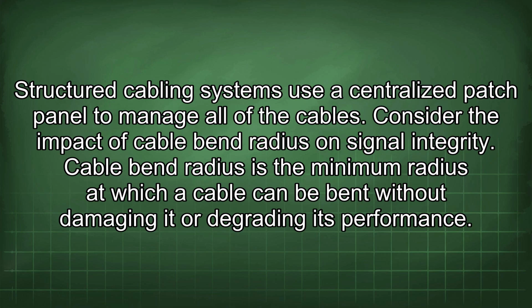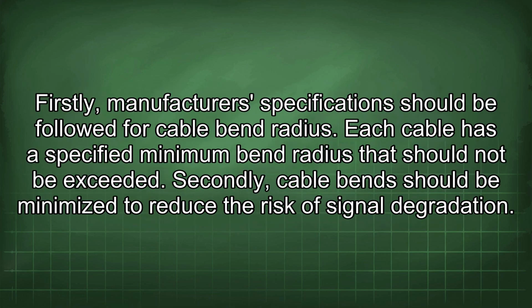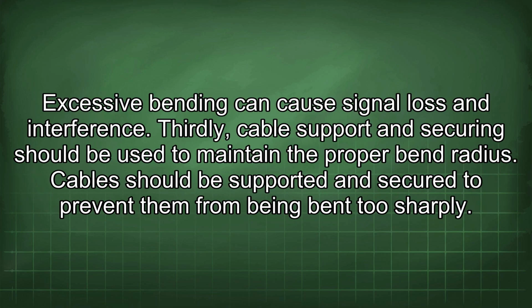Cable bend radius is the minimum radius at which a cable can be bent without damaging it or degrading its performance. Firstly, manufacturer's specification should be followed for cable bend radius. Each cable has a specified minimum bend radius that should not be exceeded. Secondly, cable bends should be minimized to reduce the risk of signal degradation. Excessive bending can cause signal loss and interference.